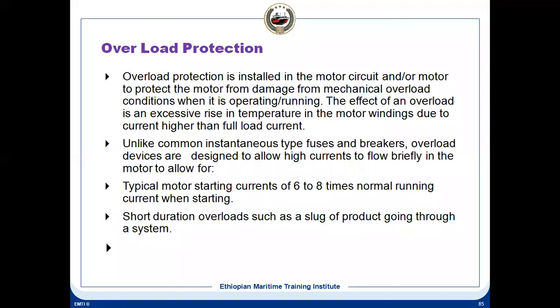Okay, overload protection is installed in the motor circuit. It is basically to protect the motor from damage from mechanical overload conditions. Like when a bearing gets jammed, or suppose your pump, which is driven by a motor, gets jammed. In this condition, there can be an overload.